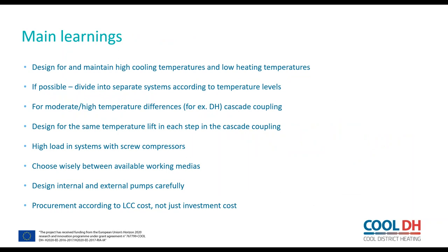I will take the main learnings, and as we have some time left, we can go a bit deeper into the study itself afterwards. But key is to have high cooling temperatures and low heating temperatures. This leads to a low difference in temperatures, thus increasing the COP. And if you can divide the systems into temperature levels, that will also be increasing the COP, as you, like I said, reduce the temperature difference. The cascade couplings is very good for high temperature differences, as you split the temperature range into more steps. And the optimal would be to have the same temperature lift in each step of the cascade coupling.